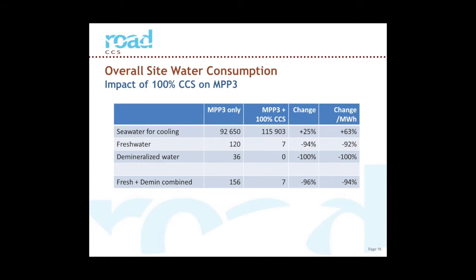So for the basic road plant, which is just under a quarter of the power plant, we get a 6% increase in cooling water usage and a 23% reduction in freshwater usage. And at full load, if we were doing 100% CCS, we would have this 25% increase on a site basis and 63% on a per megawatt hour basis, which is a big increase in cooling water. But the other water usage falls to almost nothing.